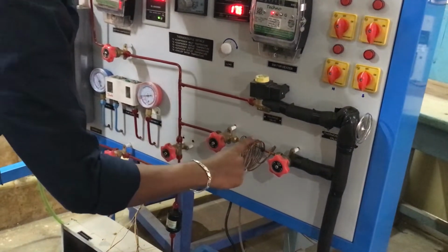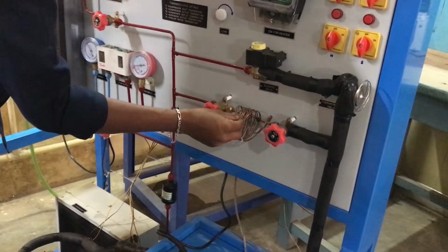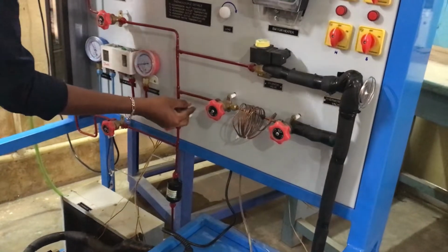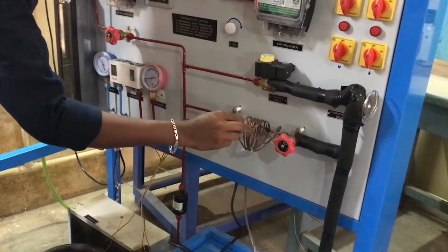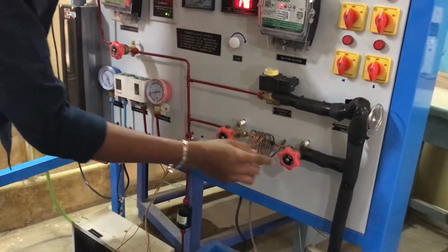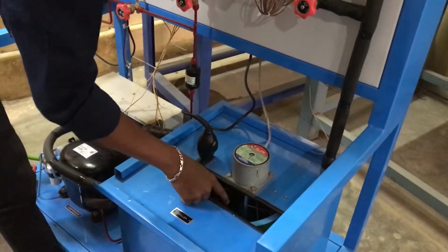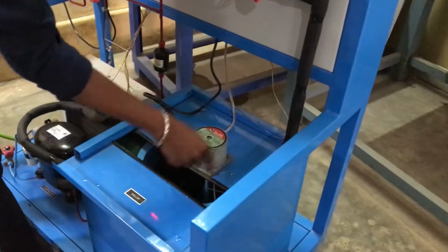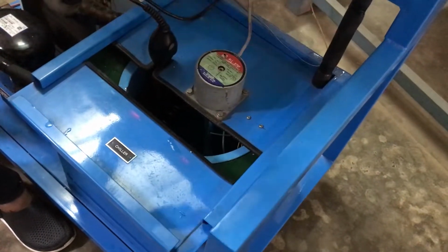You can check the cooling. The refrigerant cools here because of the reduction in diameter. So you can check it here. This is the bigger diameter. This is the smaller diameter. So there will be a reduction in pressure and temperature here. So that will be moving into the chiller part. In the chiller part, the water is at a higher temperature and the liquid refrigerant is at a lower temperature. So a heat exchange will happen.